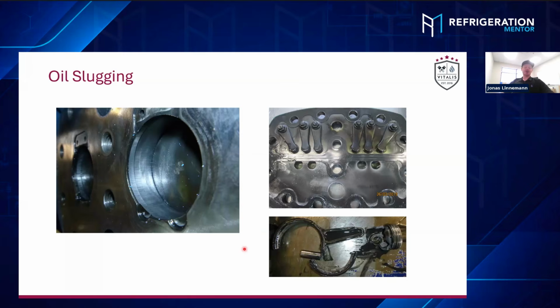I mean, it will not be dry, that must be said. We do have the oil carryover, so you will see oil in the discharge and the cylinder heads or the discharge manifolds. It also depends on the operation conditions, and there are different compressor manufacturers with different oil carryovers. Some compressors are just good with running way drier than others. Others say, hey, we want to lubricate that thing because that keeps it alive. There are different compressor designs, even if it is a reciprocating CO₂ compressor in the field. But there definitely has to be oil because that's what keeps it sealed, right? But if that chamber is full of oil, there's just too much. But you always have to have lubrication. Yeah, exactly.